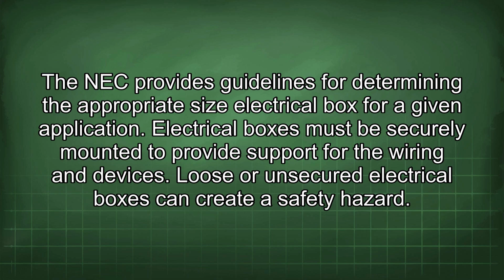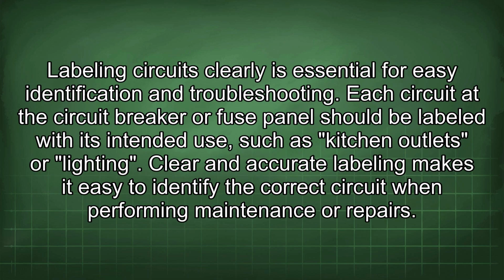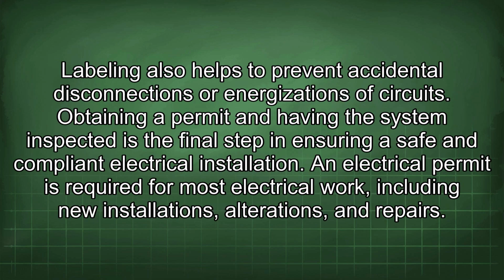Electrical boxes must be securely mounted to provide support for the wiring and devices. Loose or unsecured electrical boxes can create a safety hazard. Labeling circuits clearly is essential for easy identification and troubleshooting. Each circuit at the circuit breaker or fuse panel should be labeled with its intended use, such as kitchen outlets or lighting. Clear and accurate labeling makes it easy to identify the correct circuit when performing maintenance or repairs. Labeling also helps to prevent accidental disconnections or energizations of circuits.